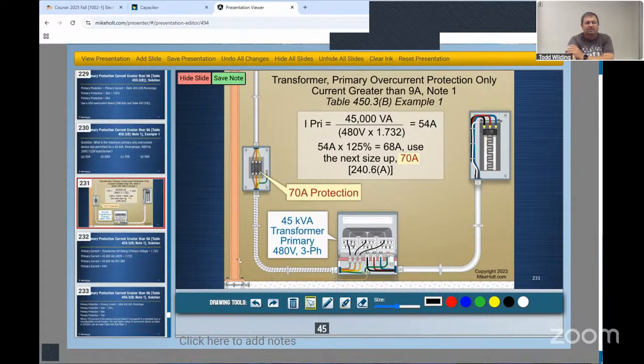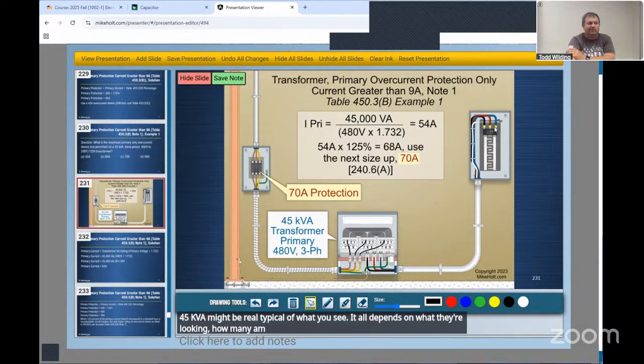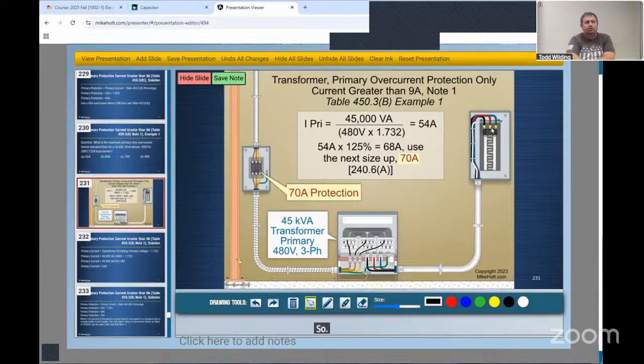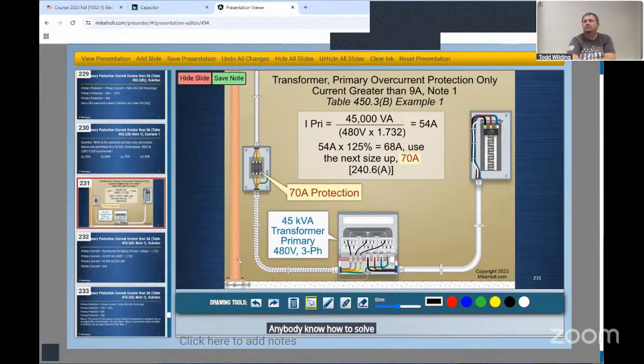45 kVA might be real typical of what you see. It all depends on how many amps they're wanting over here. So how many amps do I have over here? Anybody know how to solve for that? Power in equals power out. So if I've got 45 kVA, what was my secondary? Did it tell me? 208, right? So 45,000 divided by 208 times 1.732 gives me what?